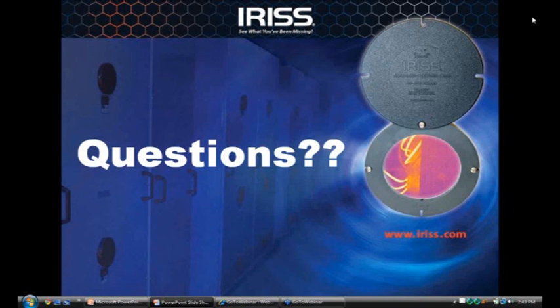Okay. Another one here: do insurance companies require switchgear inspection in facilities? You'll find yes. If I was carrying the risk for your plant, I would require an annual infrared inspection of your electrical distribution system before I would sign off on it. And you will find, depending on your carrier, with most of the companies I deal with globally, the main driver for the infrared inspection annually is the insurance company.